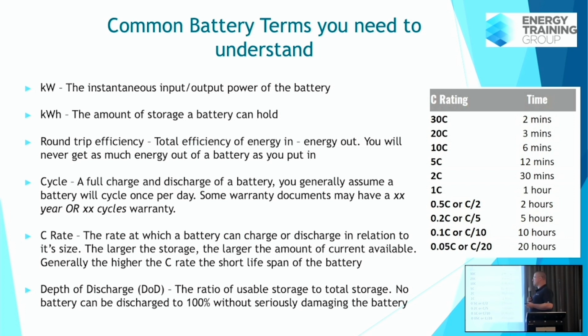C rate is something a lot of guys don't fully understand, but it's essentially related to kilowatts. It's another way of representing the max charge and discharge rate of a battery. With lithium, you're working back from what's called 1C. 1C means the battery can discharge entirely in 1 hour. So if I had a 10 kilowatt hour battery and I was discharging at 1C, I'd discharge at 10 kilowatts and it would be empty within an hour. Most batteries won't be rated to do 1C.